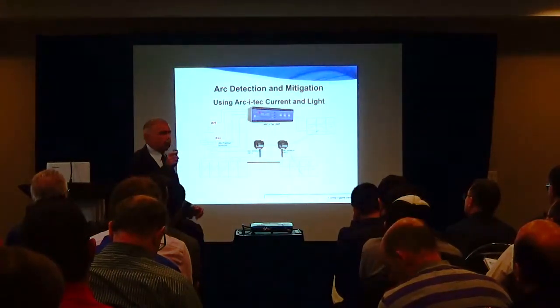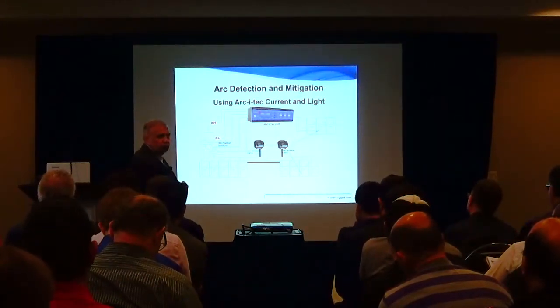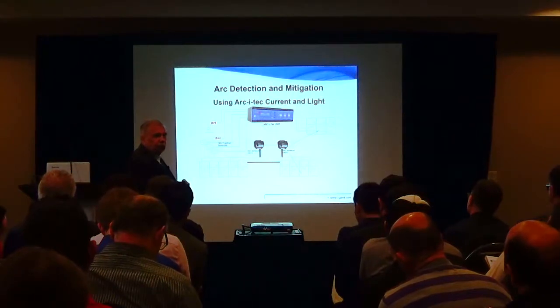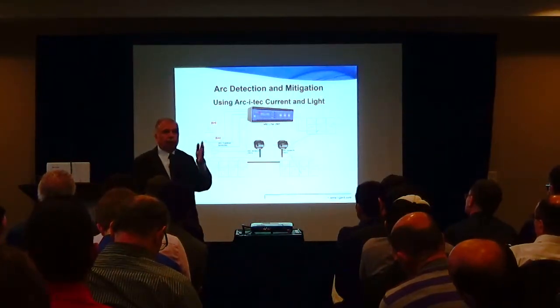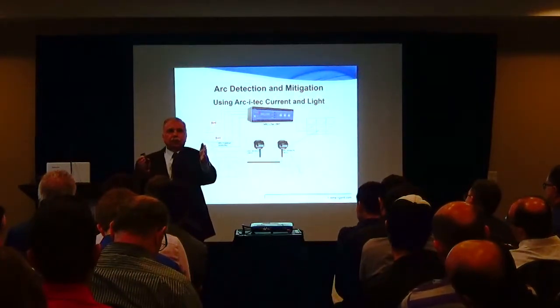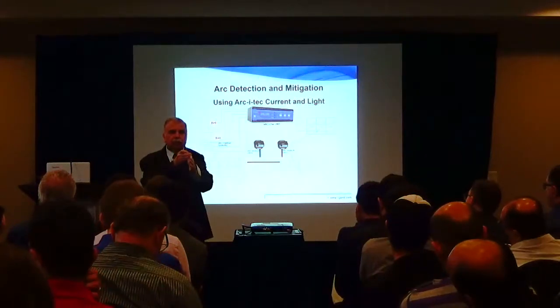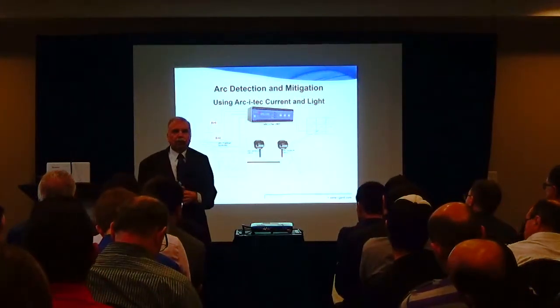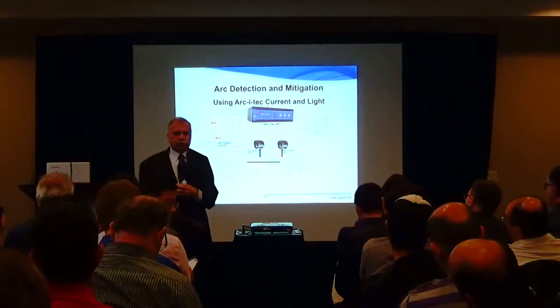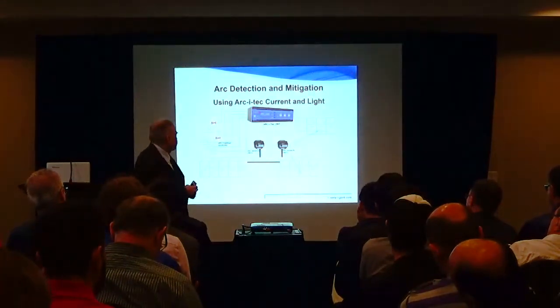Yeah, the AND function I'm going to describe here uses three-phase current sensors, CTs, current transformers, and it will say that, okay, you see an arc, but do you have a current at the same time? So it verifies that you have existence of a current to establish the tripping function. So it's only the magnitude of the current? Correct. Only magnitude of current. It's settable. You adjust it to suit.